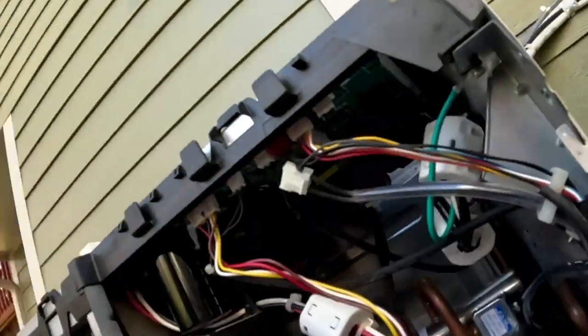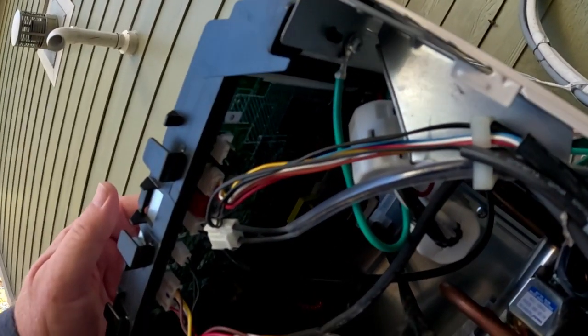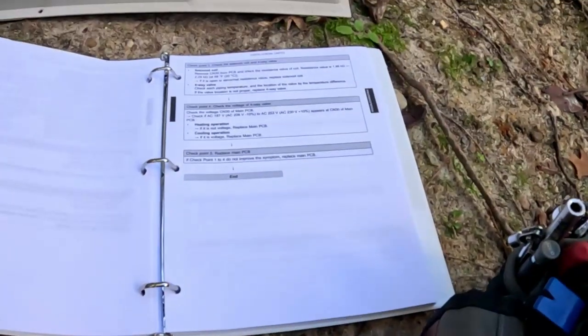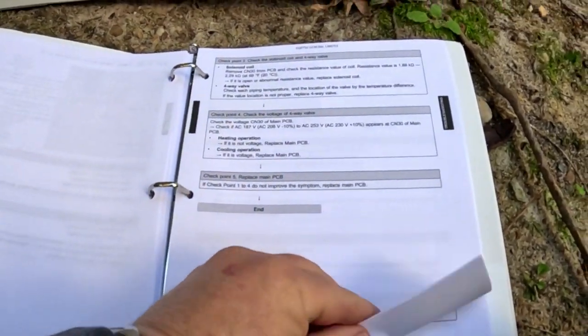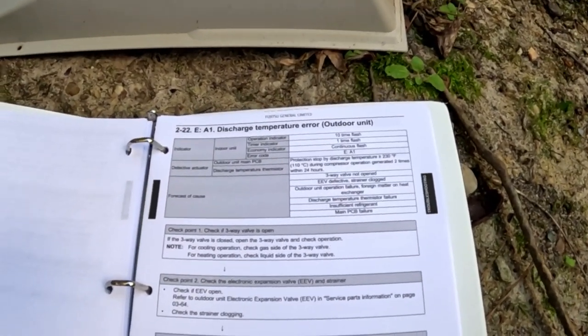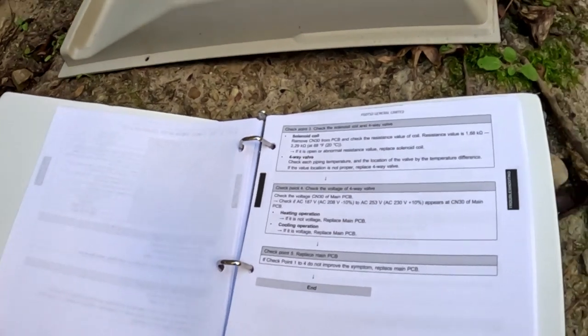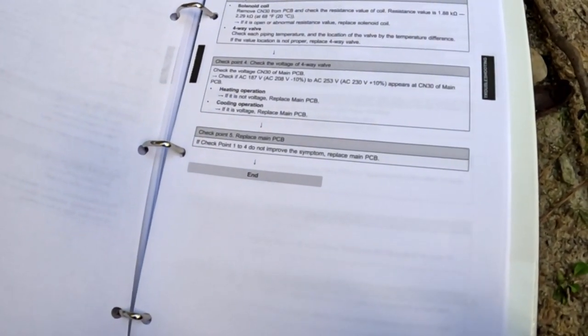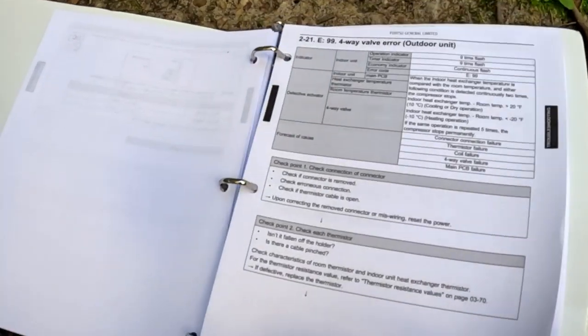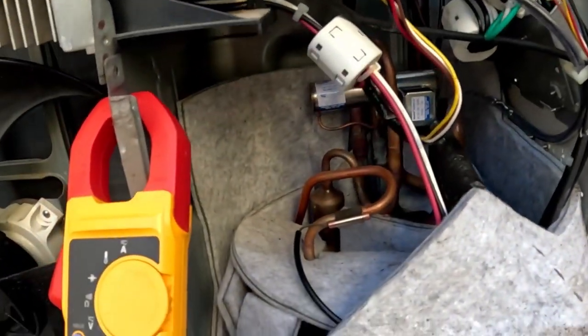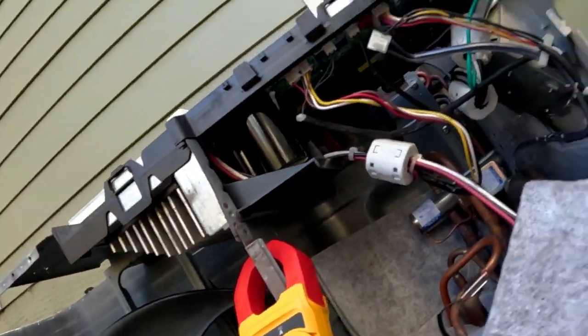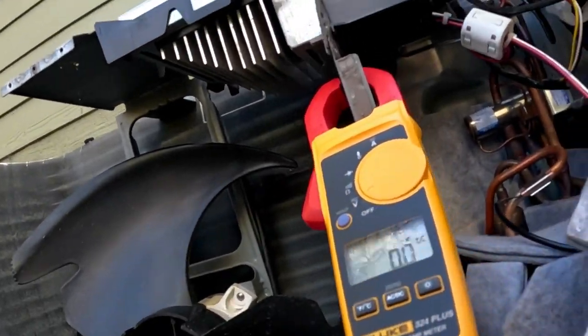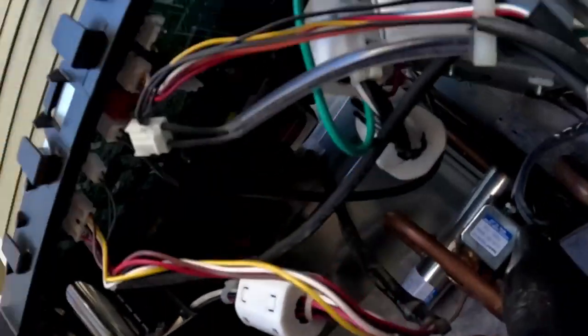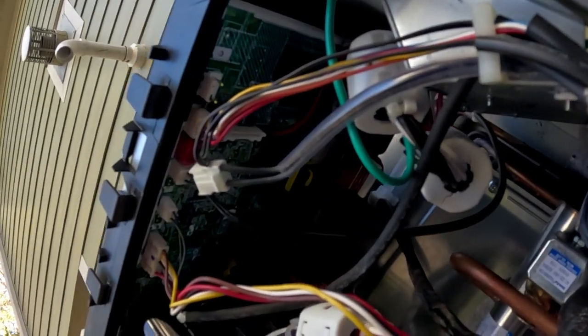I guess that's about all we can do with this. Just get them a board. If you follow their instructions, that's what it tells you. You can go in and check your temperature sensors, but he'd have had a cooling problem if the indoor temperature sensors were bad. He said it runs fine in cooling, it just won't work in heating. So evidently this thing's not switching it to heat like it's supposed to. And it's the main board. Go figure. Anyway, guys, that's a Monday morning with a Fujitsu.